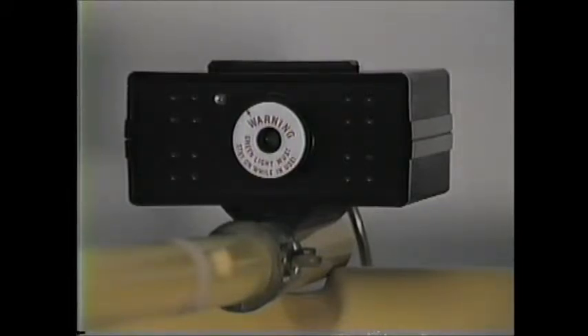The unit is calibrated for line to ground voltages of 600, 2,000, 7,000, and 11,000 volts. The banks of lights flash alternately so that it is easier to distinguish the number operating from a distance.